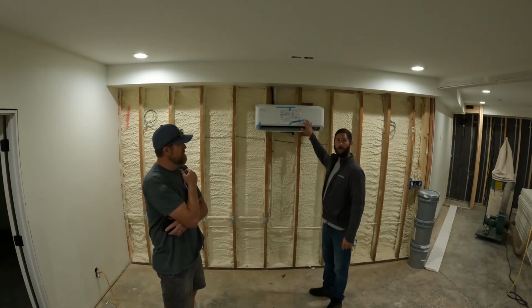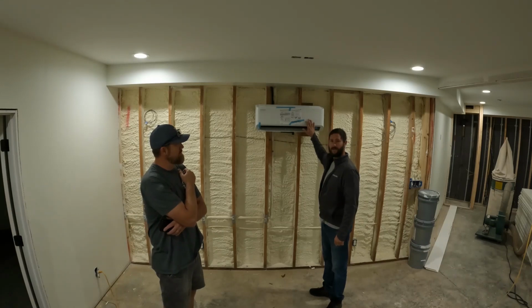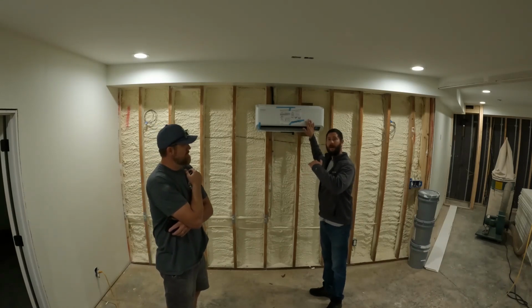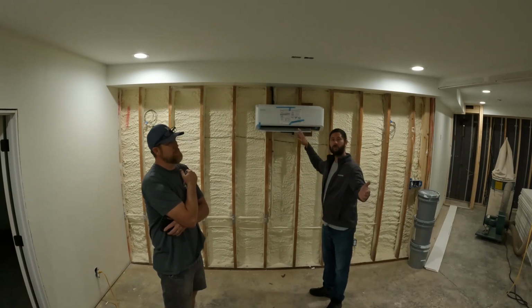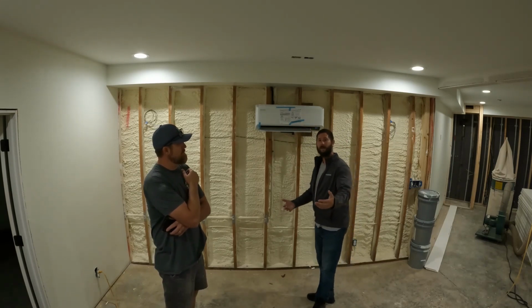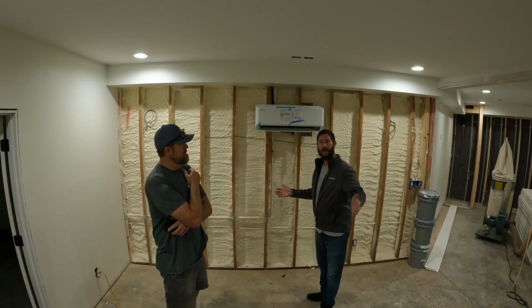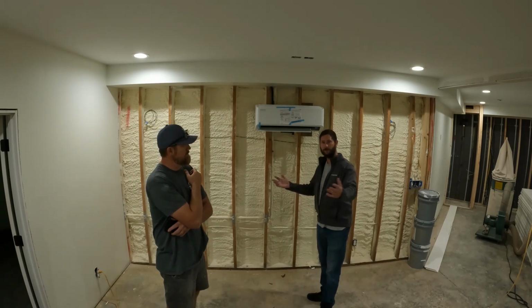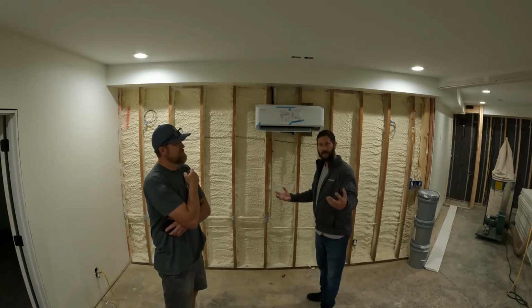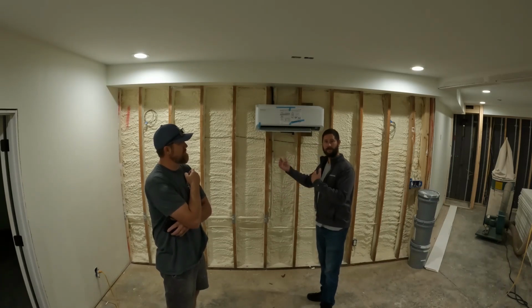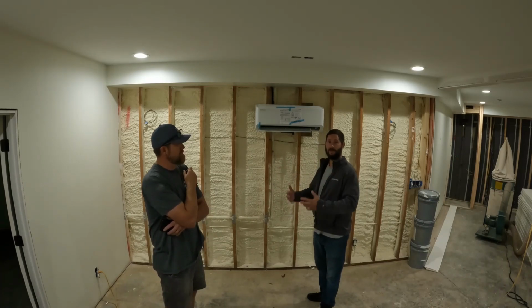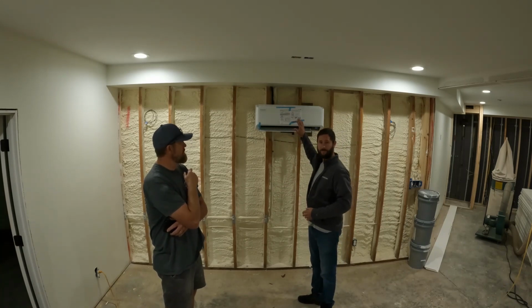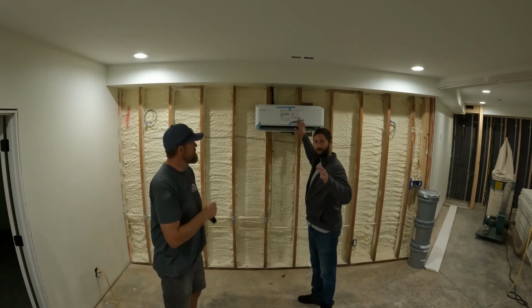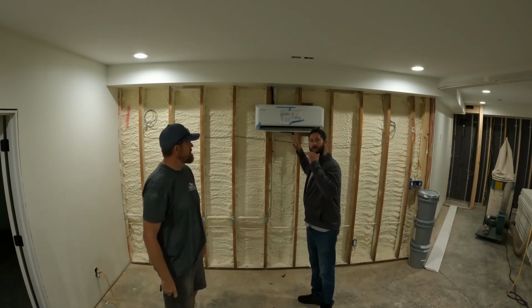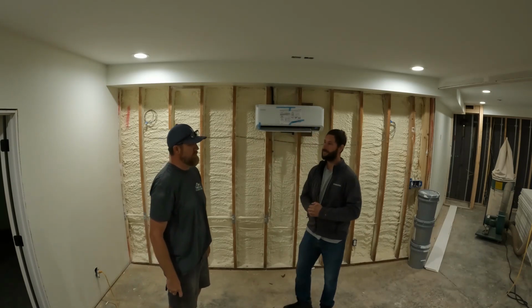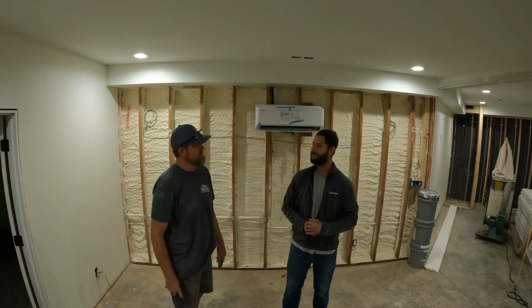Because I want to know what size, depending on what size model I use, will depend on how far the air will throw. And I want to make sure that, especially in a foam house, that we get air throughout the home. And the airflow is consistent so that we don't have mold spores or anything settling. And if we have any mold growing, we don't want that. So airflow is the key, especially when you have high humidity here in Tennessee. So I use a square foot per ton, and then I also look at the airflow charts. So that gives you a good idea of my sizing.